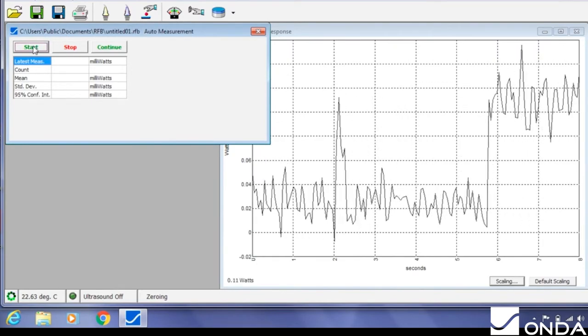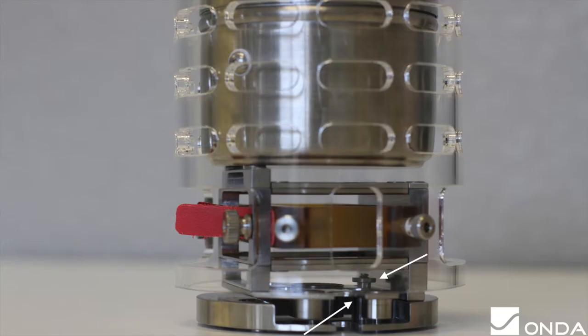When the software is checking the position sensor, the user should watch to see if the sensor is going between the lower and upper stops. If the position sensor results are not good, make sure that the sensor is properly seated, and if it is, visually check to see if the hinges are broken.